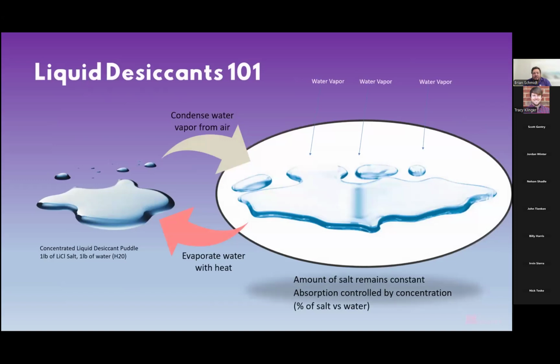So on the subject of liquid desiccants, again, we are manipulating the concentration. Water vapor from the surrounding atmosphere is at a higher pressure than the liquid desiccant itself. Therefore, that water vapor gets absorbed into the liquid desiccant, growing the puddle of water, essentially. So if I were to put a puddle of liquid desiccant on this table, over time you would see it grow as it's absorbing moisture from the air. Then we use heat to evaporate that water out, thereby reconcentrating it. So this is the cycle that I was describing, and it can cycle infinitely, right?